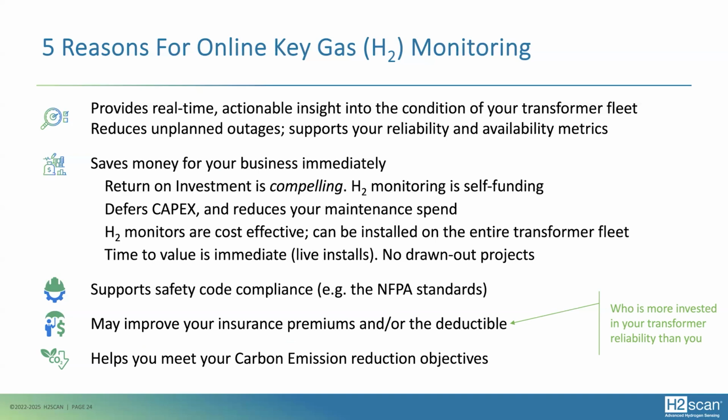We always look to what the preventable failures are, and they wrote a standard. It's FM standard 6250, if I remember correctly. If you've got a monitor with that certification, it's the right time to have a conversation with the underwriter about your premiums and/or the deductible, or what's in it for you to buy it, because you probably will get it.